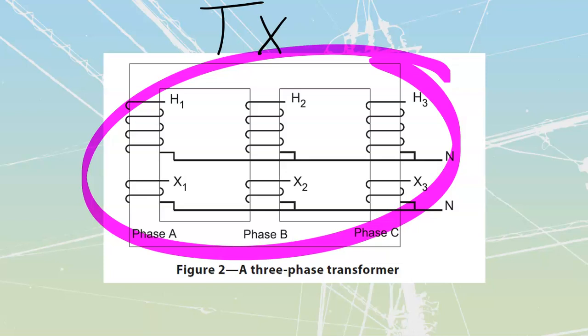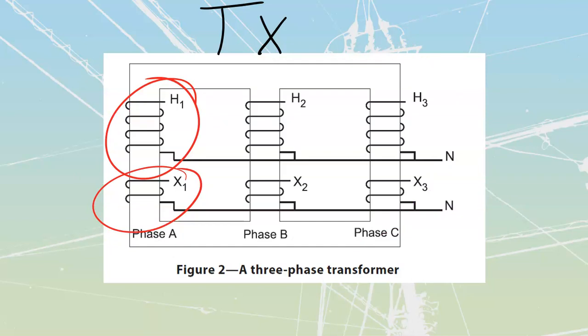On a three-phase transformer, you'll usually have the high and low voltage windings for each phase wound on the same leg of the transformer. I say usually because there's one oddball, the zigzag transformer, which breaks this rule by jumping around from leg to leg. But 99% of the time you'll see a high voltage leg composed of many windings of fine wire on the same leg or core as the low voltage winding, which is made up of fewer windings of thicker wire. You should be able to identify when you've got a high voltage winding versus a low voltage winding: the high voltage carries less current, so it's a thinner wire, but because it's high voltage it has thicker insulation, and because it's based upon transformation ratios, it has many turns.